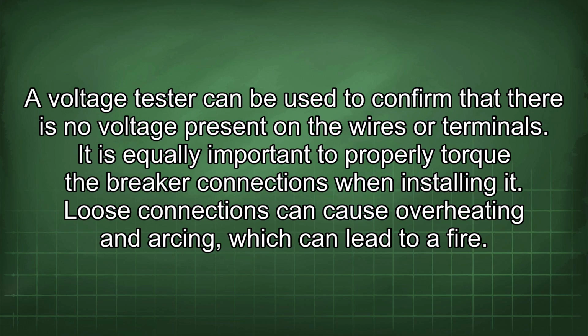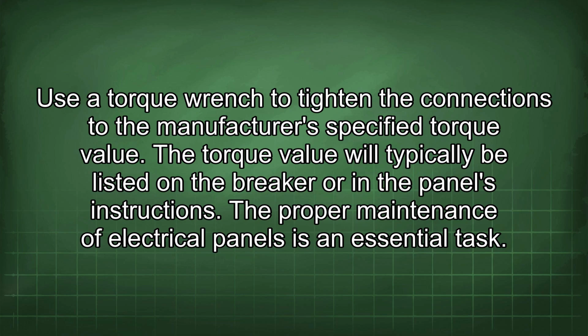It is equally important to properly torque the breaker connections when installing it. Loose connections can cause overheating and arcing, which can lead to a fire. Use a torque wrench to tighten the connections to the manufacturer's specified torque value. The torque value will typically be listed on the breaker or in the panel's instructions.